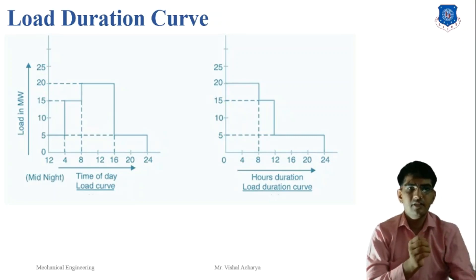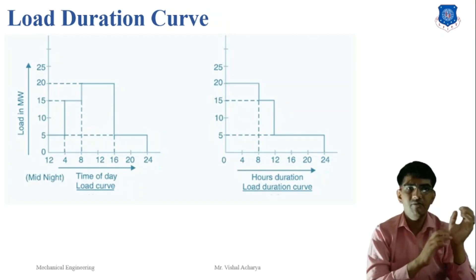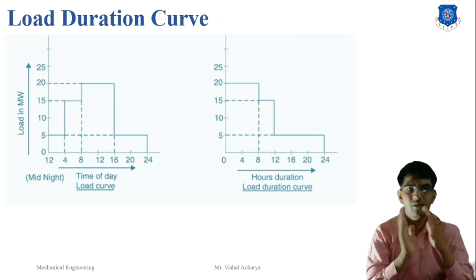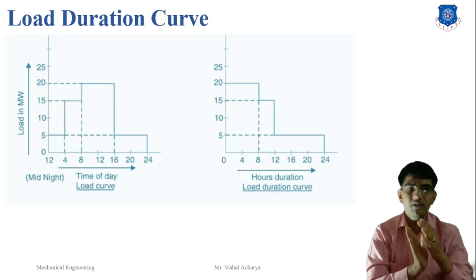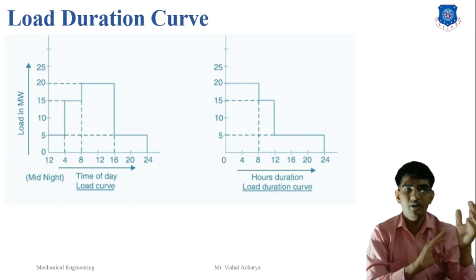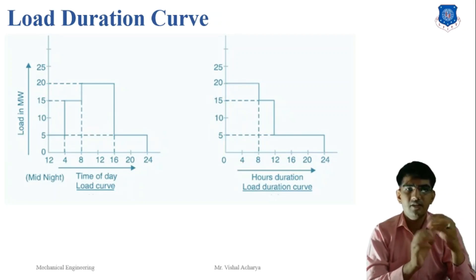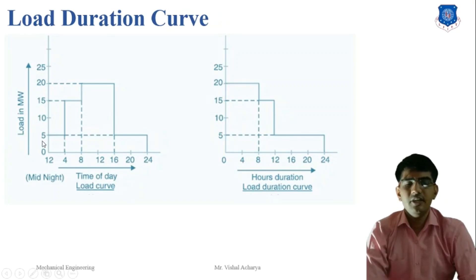Some information from the load duration curve: first, it gives the minimum load present throughout the specified period. Second, it helps in the selection of the base load and peak load power plant. Any point on the load duration curve represents the total duration in hours for the corresponding load and all loads of greater values. The area under the load duration curve represents the energy associated with the load duration. The average demand during a specified period such as a day or month can be obtained from the load duration curve.